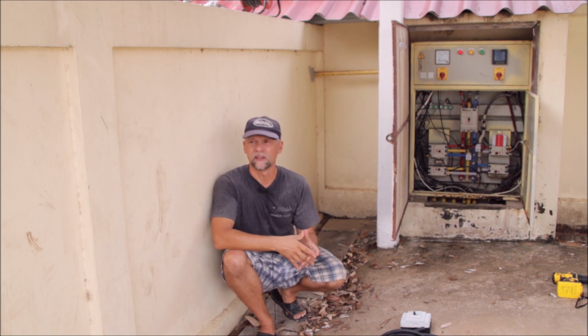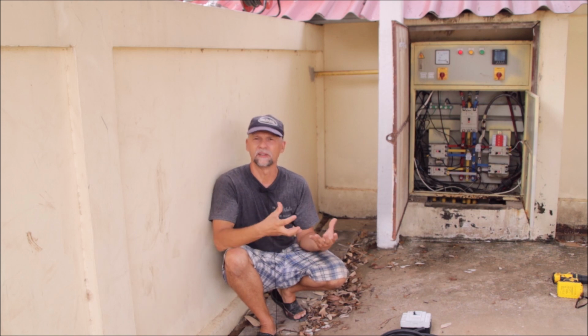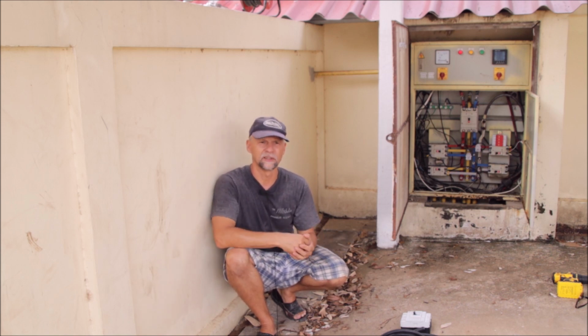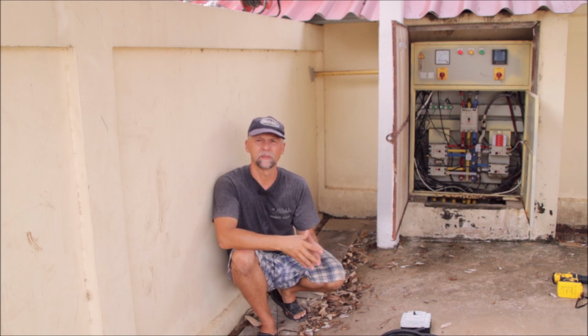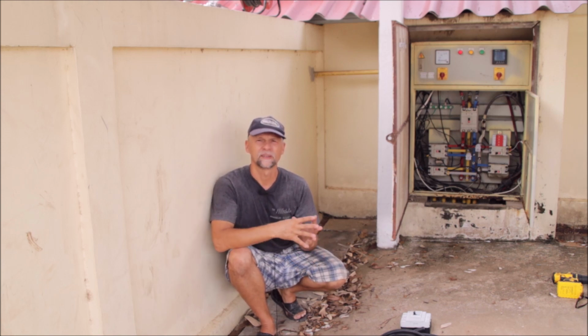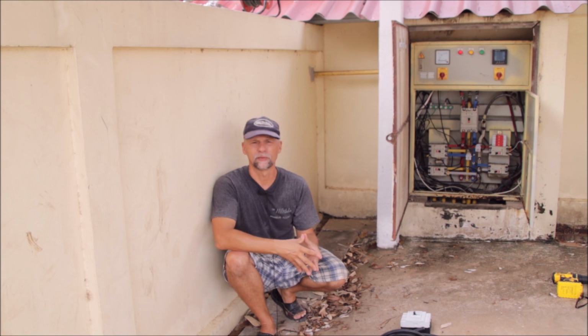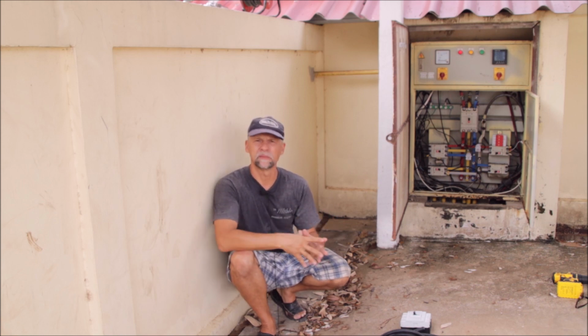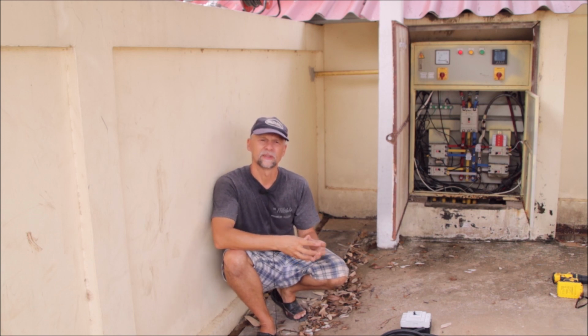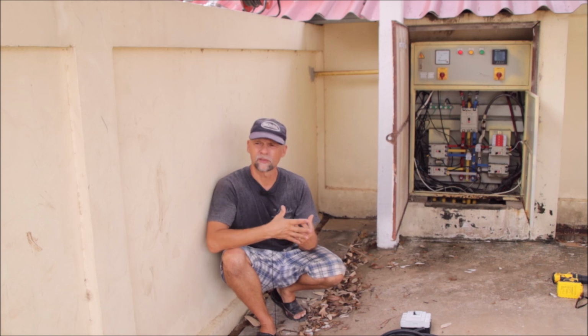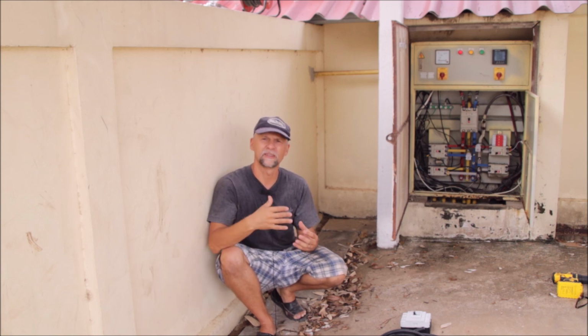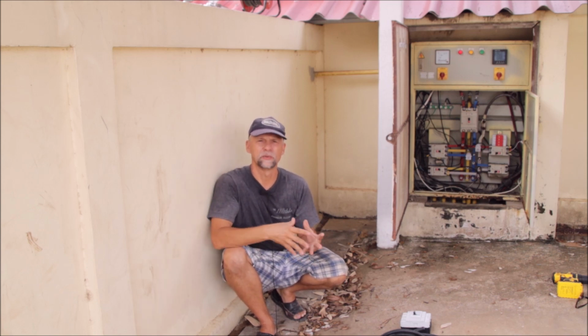So if an excavator is digging up a cable, or somebody carelessly digging something and hitting a cable, causing a short circuit, then these sorts of fuses or breakers have to trip. But how do we know how to dimension these breakers? It has something to do, of course, with the cables you use and the distance to the next distribution point.